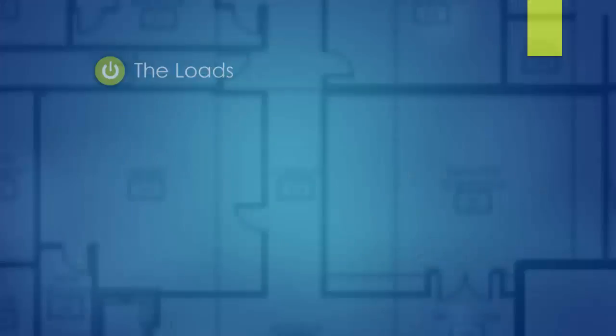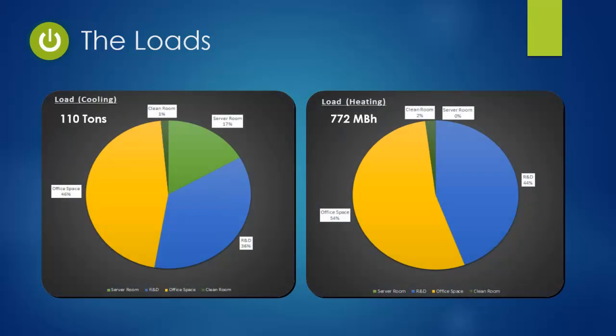The building loads were calculated in Trane Trace 700, and the percentages and reasons for the load in each category are as follows. The office space makes up 46% of the cooling load and 54% of the heating load. This is due to envelope loads and the size of the space. Next, the research and development space makes up 36% of the cooling load and 44% of the heating load, which is a result of the large amount of outside air needed due to high exhaust rates.